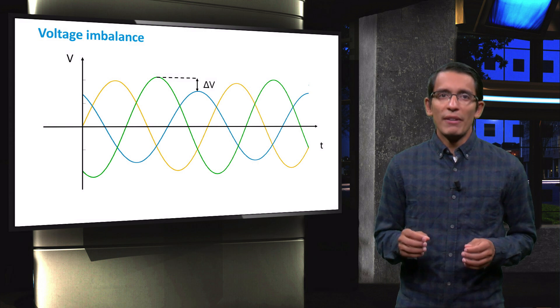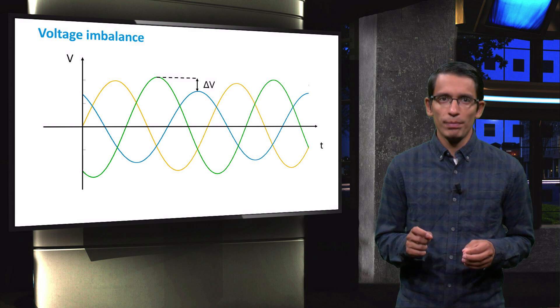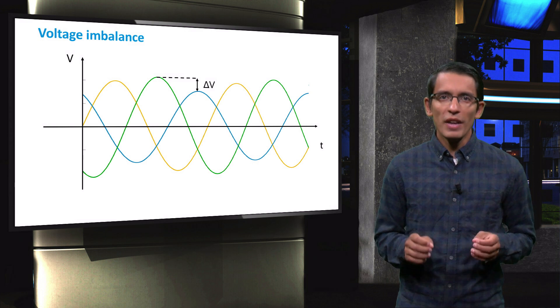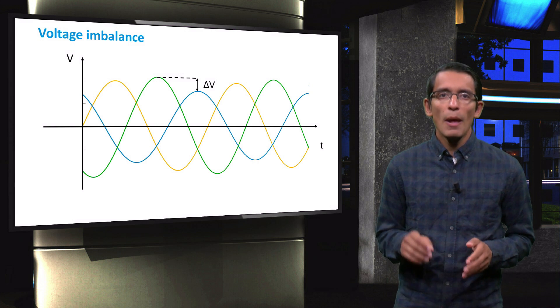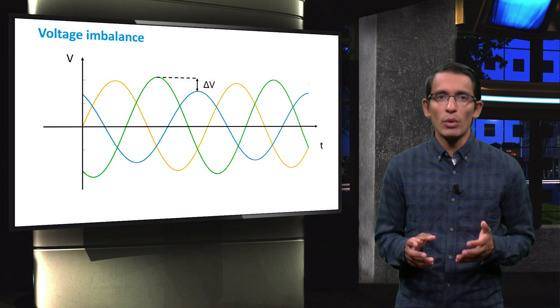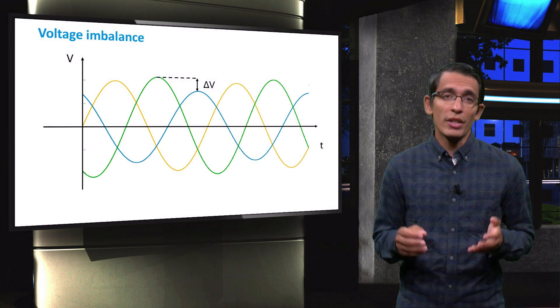Generally, the difference between the highest and the lowest voltage should not exceed 4% of the lowest voltage. Single-phase PV systems installed disproportionately on one of the three phases may cause severely unbalanced networks. Damages to control systems and damages to transformers can also occur.